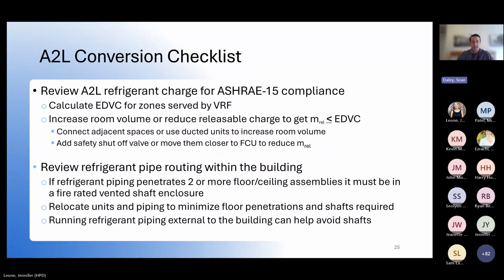That slide was just general design considerations for designing A2L VRF systems. Here I wanted to put the two major focus points if you had to convert a project over from R410-A to A2L, either R32 or 454B. The first is the refrigerant charge for ASHRAE 15 compliance. You're going to have to calculate the EDVC for the zone served by the VRF. Again, that's the max charge allowed to be leaked into the space. Based on that, you're going to have to increase room volume or reduce the releasable charge so that your releasable charge, MREL, is less than or equal to your EDVC.